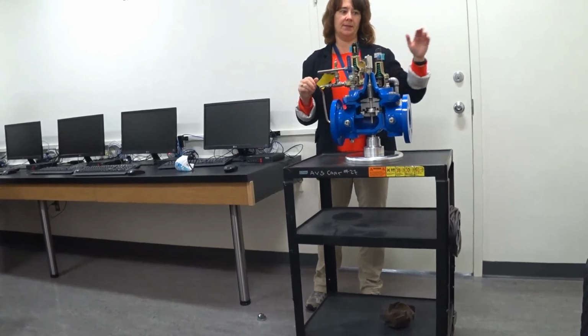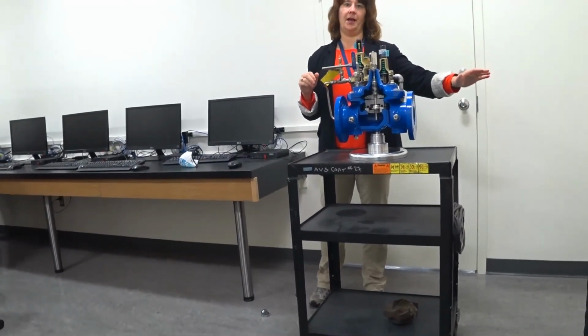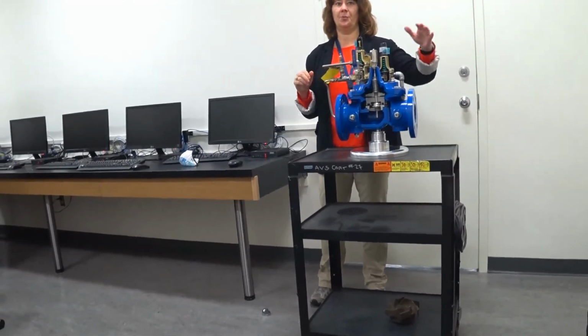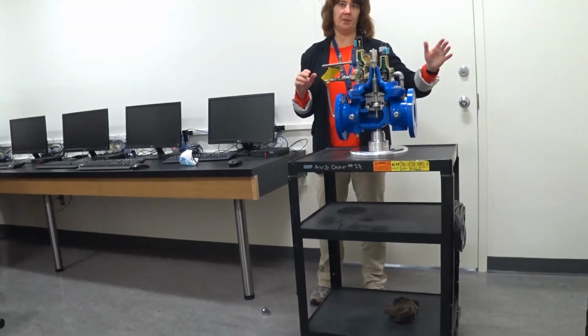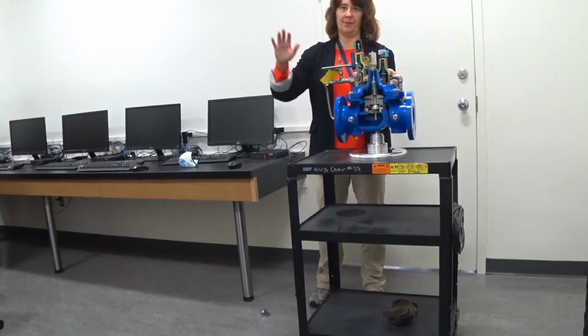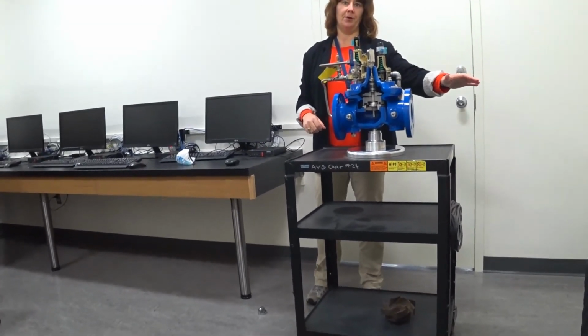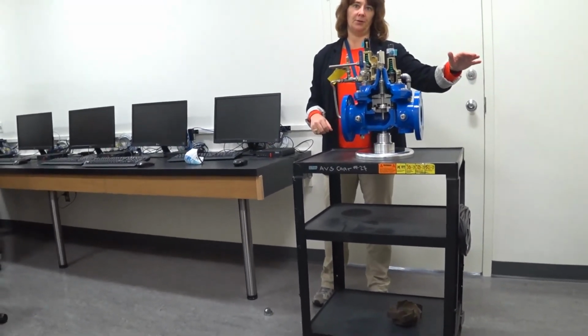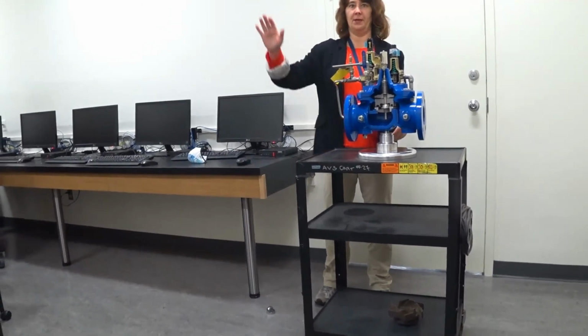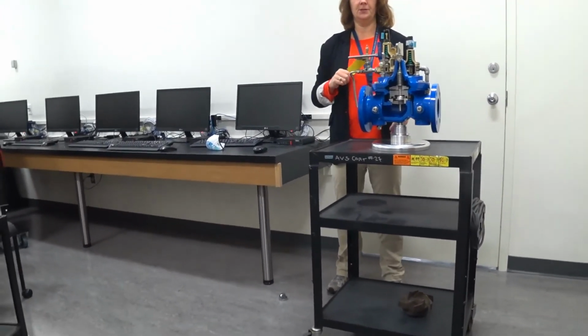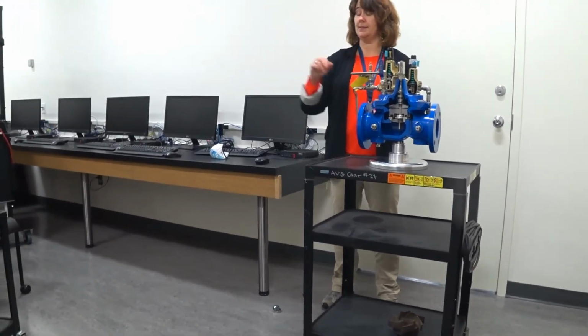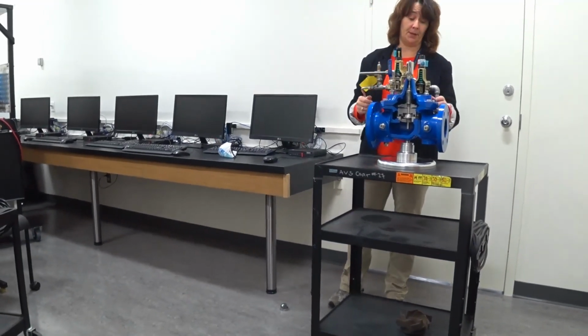So we really want to have that neighborhood have the pressure that it needs. And what that means is the lower area is going to have to get its water from another part of the gridiron distribution. So it just says, okay, this is my priority here. I am connected to this downstream neighborhood, but they have other ways of getting water into their neighborhood. And it can't come from here at the expense of this neighborhood. So that's why we put these in instead of just a standard PRV.